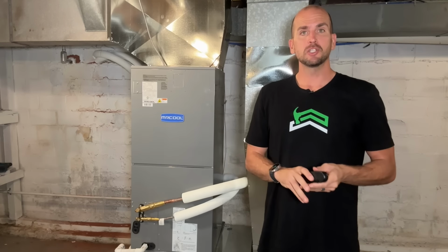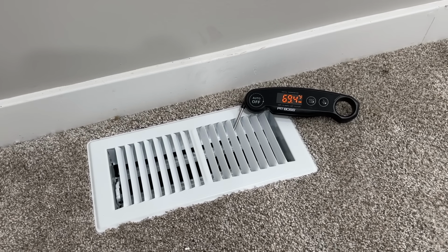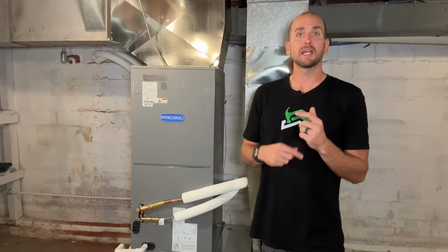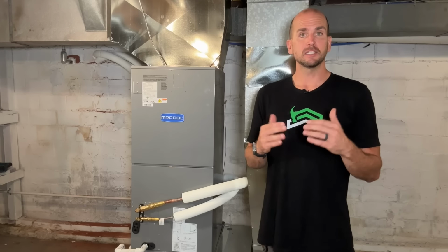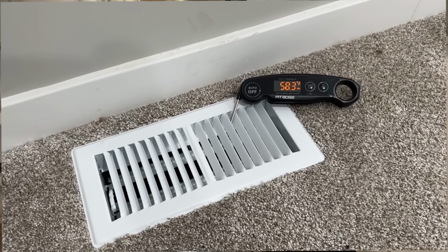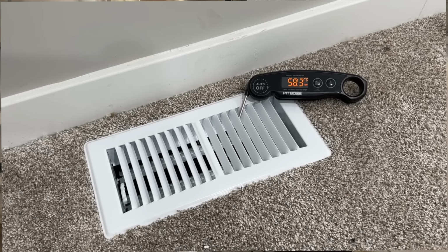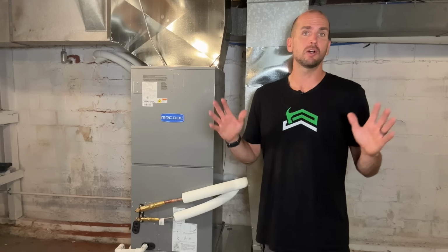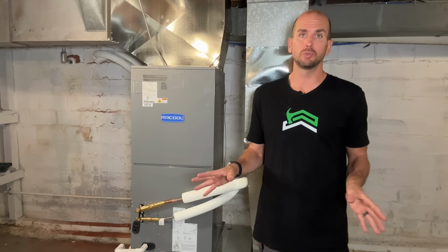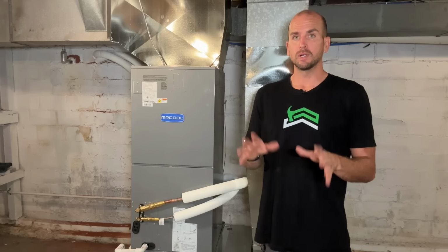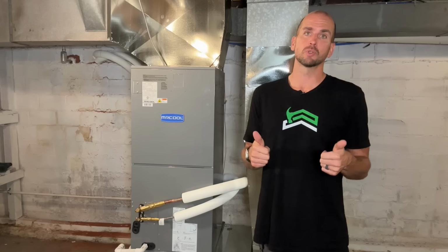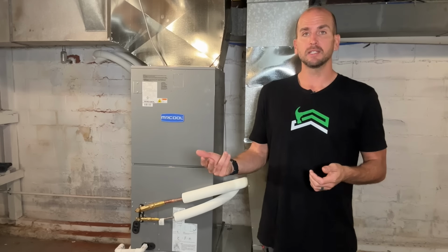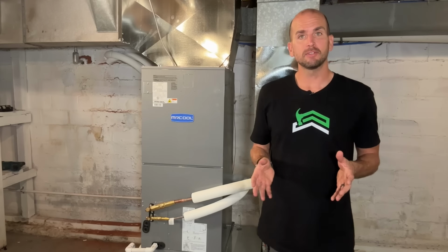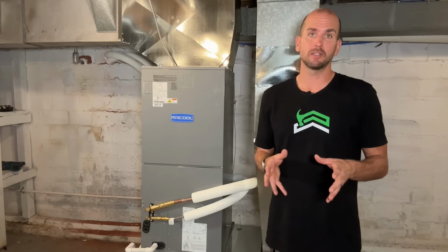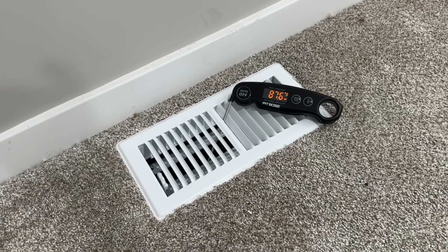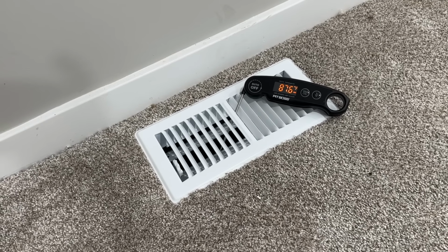Initially I was only getting a little under 70 degrees Fahrenheit air, but after about 5 minutes, I saw that progressively cool down to where it settled out at about 58 degrees Fahrenheit coming out of the vents. Overall, I was happy with that temperature and it really started cooling down the space. Once the AC was confirmed working, I flipped it over to heat and did the same test. Again, I gave it a little time and I saw the air coming out of the vent get up to about 87 to 88 degrees Fahrenheit. Again, very effective at heating.